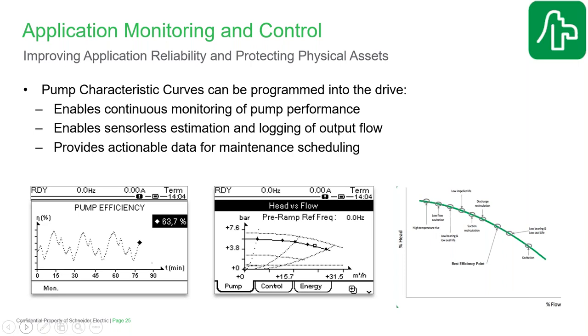That can be tracked from the drive, and you can see that performance in the characteristic curves or just in efficiency monitoring, and that's a critical data point for performance metrics and for predictive maintenance calculations. It enables you to actually measure how much money efficiency drops in your operational conditions are costing you, and use that cost calculation to make maintenance decisions.